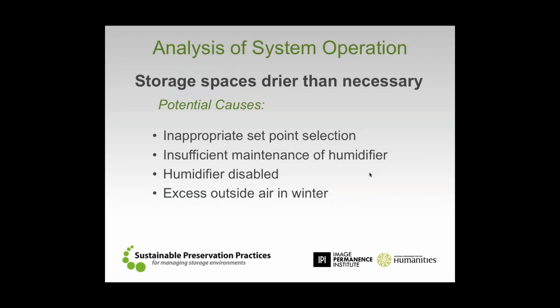Those storage spaces, if you see too much dryness or if the humidifier doesn't appear to be keeping up, watch for the set point on the humidifier, make sure that it is high enough. Check to see whether or not the humidifier is functioning properly. Unfortunately, humidifiers are a classic case of maintenance hogs.